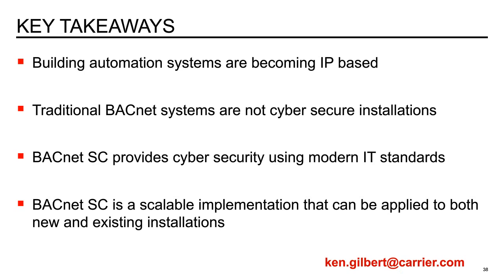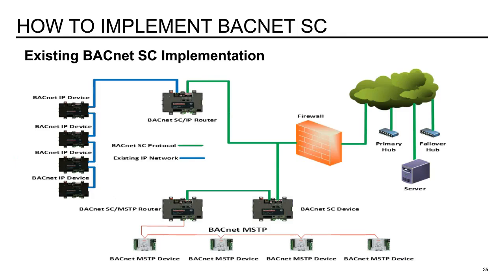And let me add to that. In order to accomplish that, if you were doing a new installation, the new devices would need to be BACnet SC devices that you're connecting to. If you have existing BACnet systems, like we talked about in this slide here, you need to put in BACnet SC routers to whatever protocol, whether it's MSTP or IP, and then those devices would talk to the server through BACnet SC.